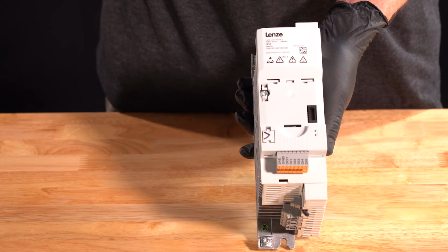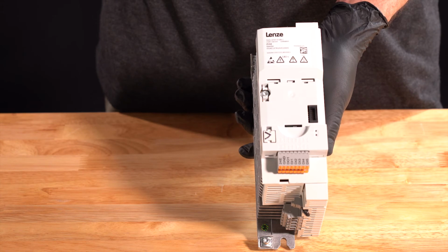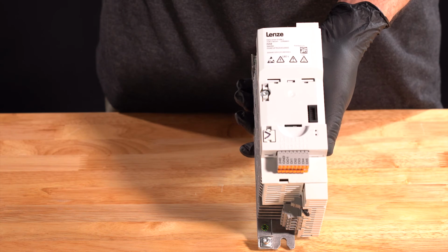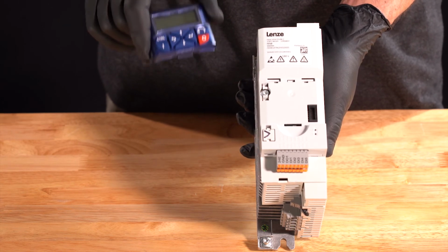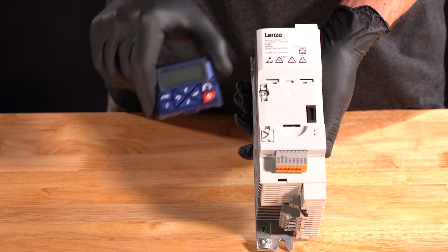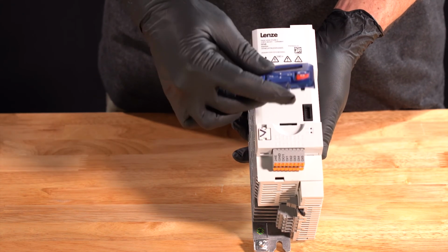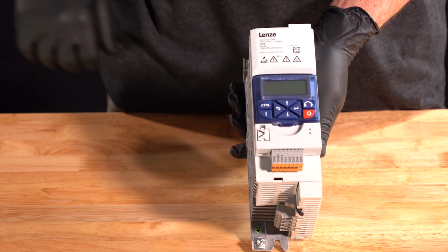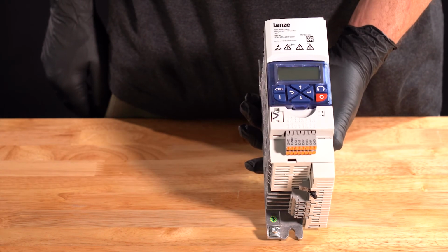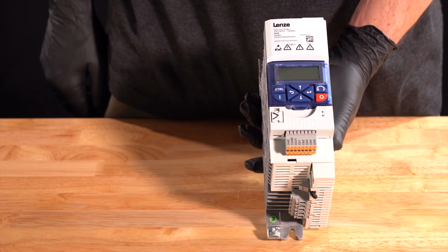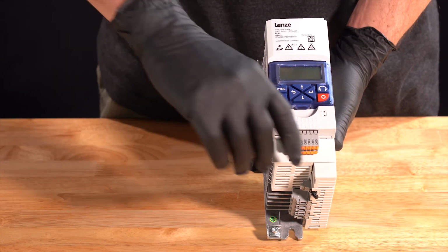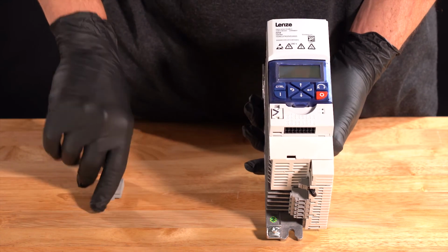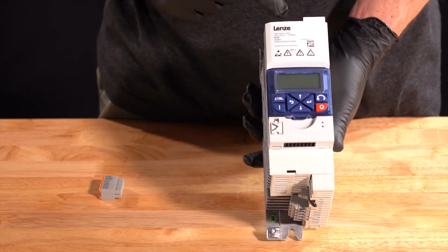If you need to replace the VFD, we've set you up for success. The VFD shows up pre-programmed with all the same settings. It's truly plug and play. The only thing you'll need to do is remove the digital display from your old VFD and insert it into the new VFD. When replacing the VFD, for the most part, you won't have to do any wiring. Simply pull out the contact blocks and set them aside and use the ones that are already installed in your machine.